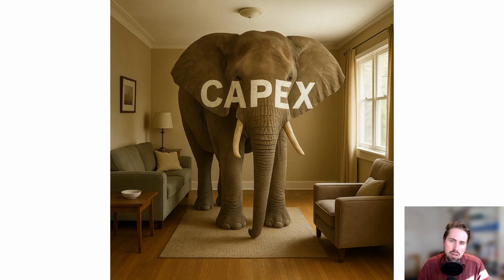Now, before we start, I want to discuss the elephant in the room, namely the capex, the capital expenses, the investment cost of ground source heat pump. Because it is typically true that a ground source heat pump, due to the fact that you also have to install the geothermal part, is more expensive from an investment point of view than air source heat pumps. Now I say mostly because it's not by definition the case. For example, and we will discuss noise later, in some regions, densely populated areas, if you install air source heat pumps, you have to take into account certain measures in order to make sure that the noise level is below a certain threshold. And this extra investment cost sometimes compensates for the higher investment cost of geothermal systems.